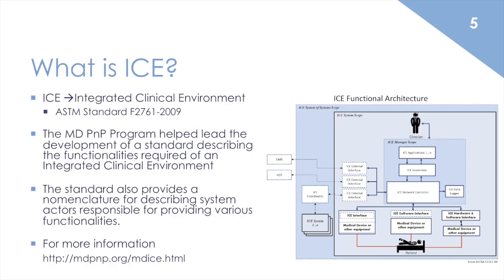So let's take a step back for a moment. Before there was OpenICE, there was ICE. The acronym ICE stands for the Integrated Clinical Environment, which is described in ASTM standard F2761. The program helped lead the development of this standard to provide a common language or nomenclature for describing interoperable systems of medical devices. The standard also lays out functionalities required of such a system and assigns actor names to different groupings of functionalities.